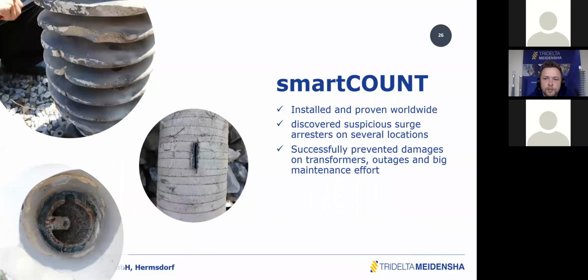Now we have installed and proven the smartCOUNT worldwide and already discovered suspicious surge arresters on different locations. And I can tell you some surge arresters have been replaced now, and we found some very suspicious items, especially on the pictures you see here. We have that one surge arrester which has flashed over due to surface contamination. We have this surge arrester breakdown due to zinc oxide aging. We see the break in this zinc oxide block here, which is wrapped with this fiberglass tape. And on the left low end, we have the surge arrester which was exposed to humidity ingress. You see the corrosion already taking place on the metal parts inside the surge arrester.